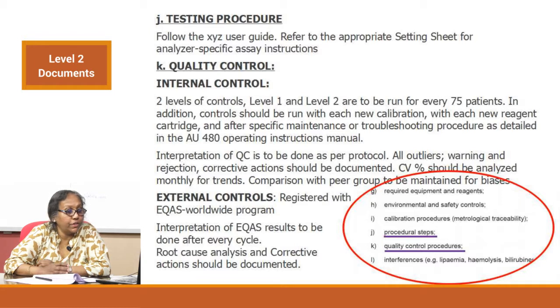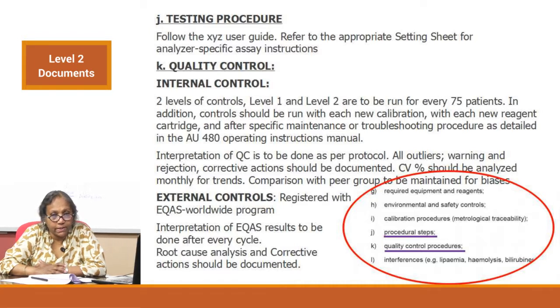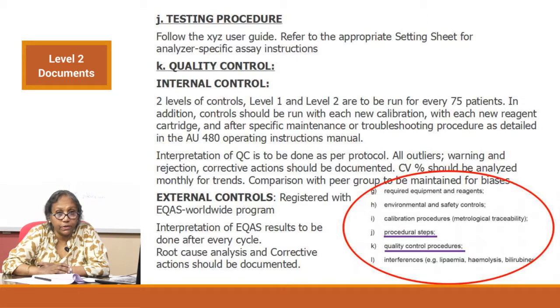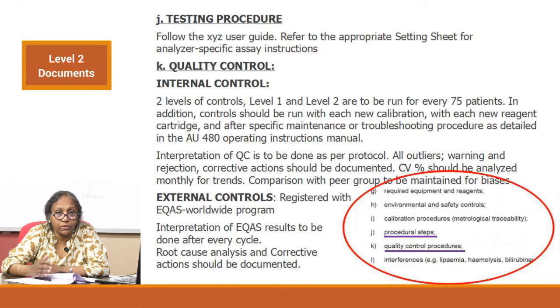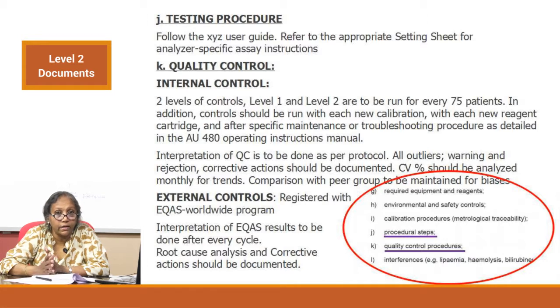Sub-clause K is quality control. Under quality controls, you must define the internal quality control procedures and the external quality assurance procedures — how to do both. Many labs create a separate SOP exclusively for quality controls, which is a good idea — describing the details of your internal and external quality control programs: how to reconstitute QCs, how to run them, the periodicity of review, and which rules frontline staff versus the supervisory team will look at. Alternatively, you can include it within the same equipment SOP, with common calibration and QC reconstitution steps written together under one heading.